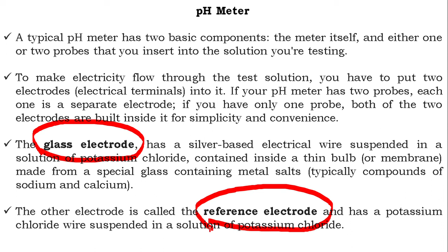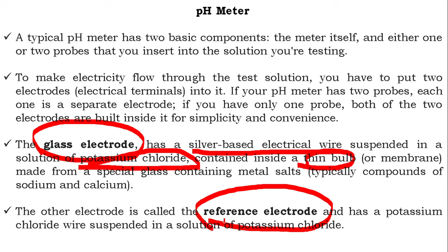The glass electrode consists of a silver based electrical wire suspended in a solution of potassium chloride, and it is present in a thin bulb or in a membrane. Actually in our machines we are having a thin bulb, and this thin bulb is made from special glass materials. The other electrode is a reference electrode. It has a silver wire in it, suspended in a solution of potassium chloride.